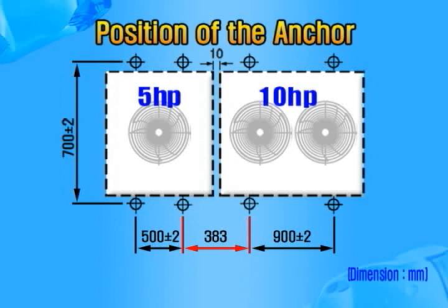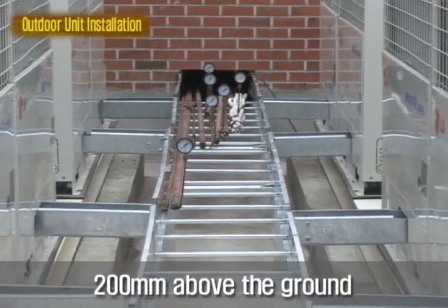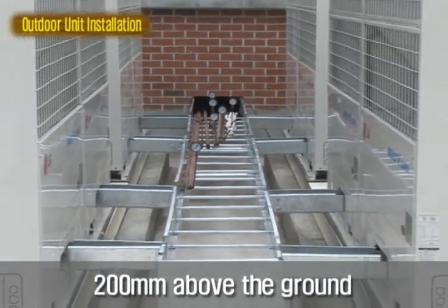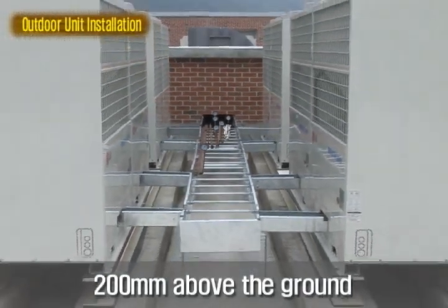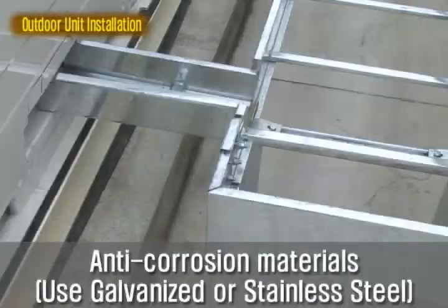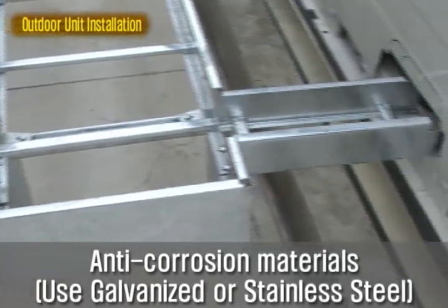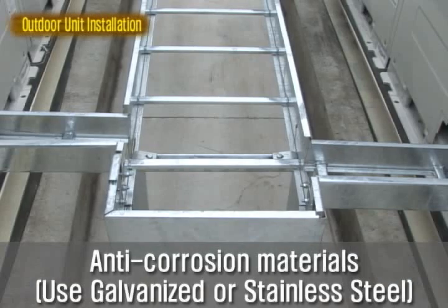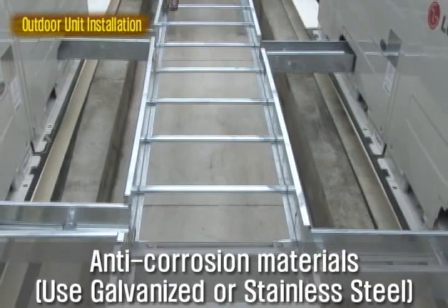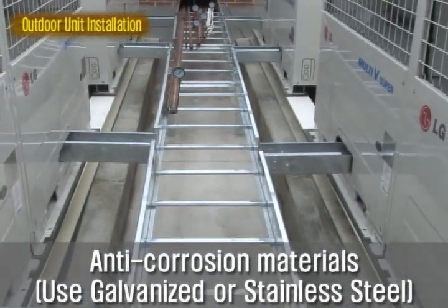If you combine more than 2 outdoor units, the distance of the anchor bolts between each product is 383 millimeters. Install a tubing tray with anti-corrosion materials such as hot dip galvanized or stainless steel above 200 millimeters from the ground to protect the refrigerant pipe and wirings from drainage, moisture, and corrosion.